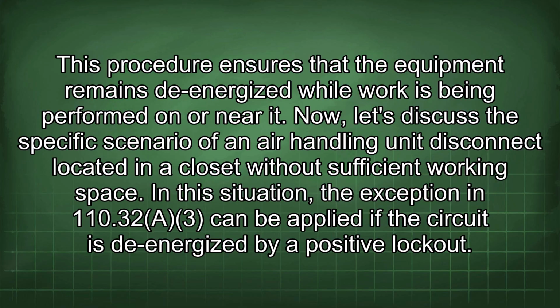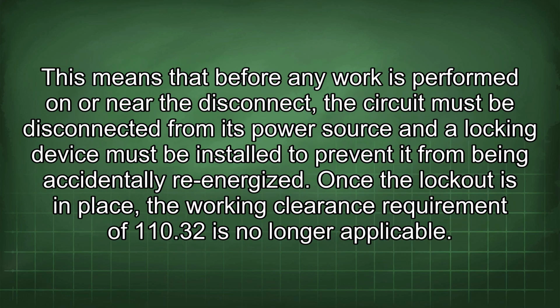Now, let's discuss the specific scenario of an air handling unit disconnect located in a closet without sufficient working space. In this situation, the exception in 110.32a3 can be applied if the circuit is de-energized by a positive lockout. This means that before any work is performed on or near the disconnect, the circuit must be disconnected from its power source and a locking device must be installed to prevent it from being accidentally re-energized. Once the lockout is in place, the working clearance requirement of 110.32 is no longer applicable.